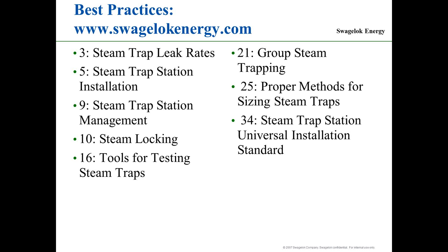Because vendors tell me, my steam trap doesn't leak. There's a leak rate of 1 ounce per 100 years. You're telling me your steam trap has a lower leak rate than that? Come on. Tell me what your leak rate is. You know, it's per PTC 39. Everything leaks. So know the leak rate.